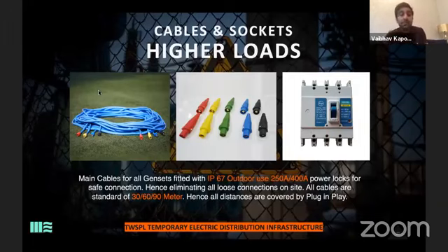So what's happening - these power locks, the sockets still come till 125 amps. When I'm dealing with higher loads, meaning 250 amps, 400 amps, then I start using these power locks. If you read, these power locks are IP67 rated. Why IP67? Because it has to be watertight, since most of the time these cables are outside - let it be your indoor show or outdoor show, these cables are always kept outside. So I have to protect them from rain, dust, rodents, or any foreign object entering into this.